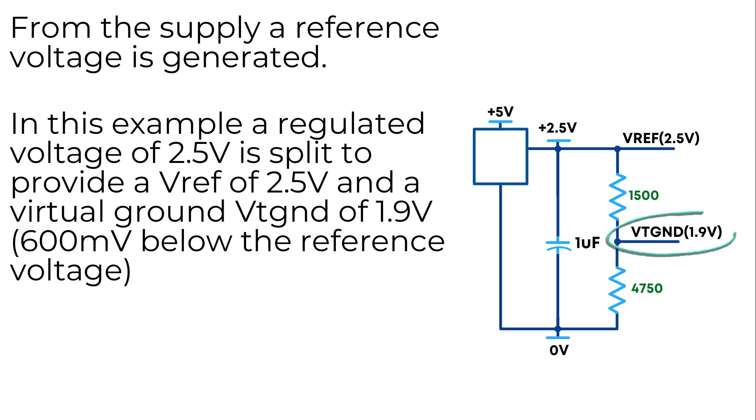This voltage is then further split by use of a resistor network to provide a VREF of 2.5 volts and a virtual ground voltage of 1.9 volts, a difference of 600 millivolts. This 600 millivolts difference in potential is what allows the lead-free oxygen sensor to work.